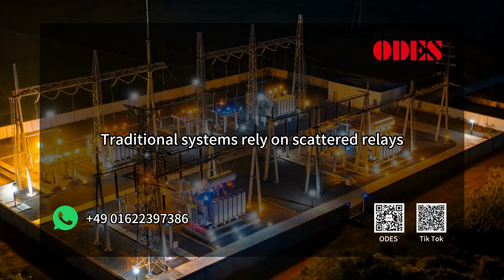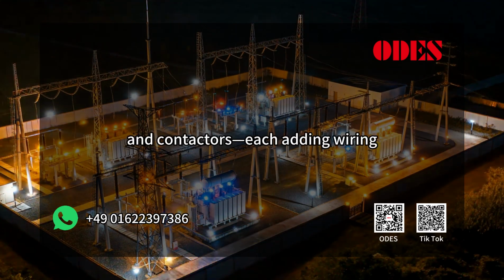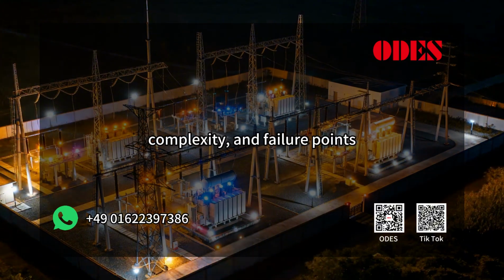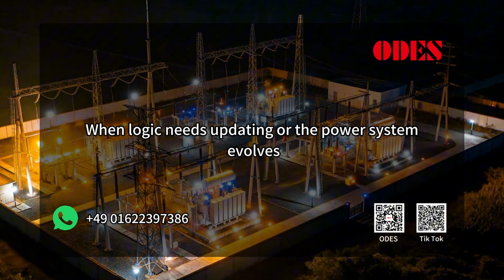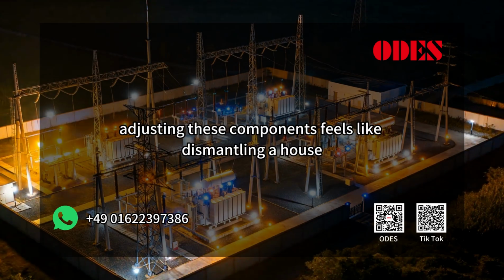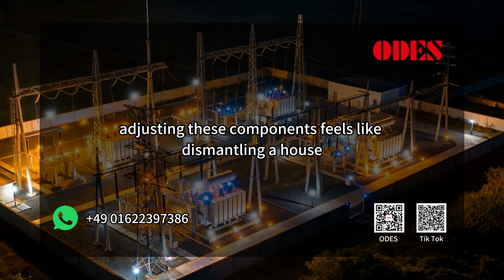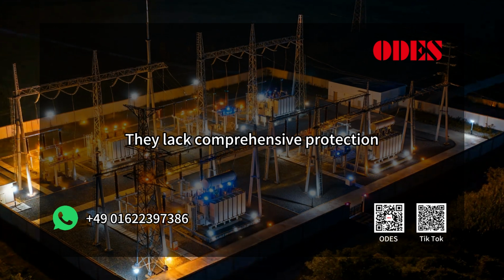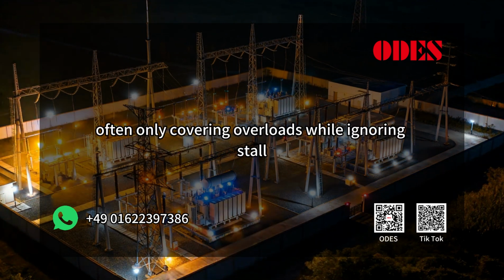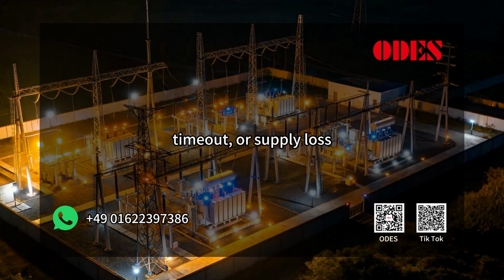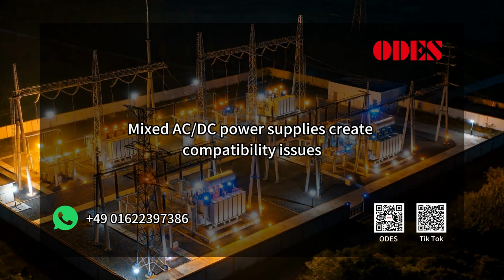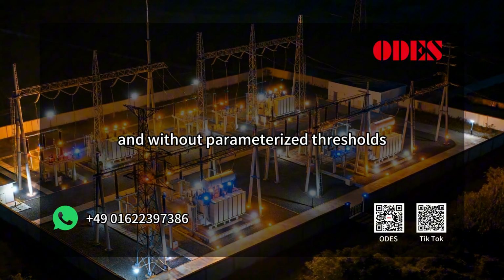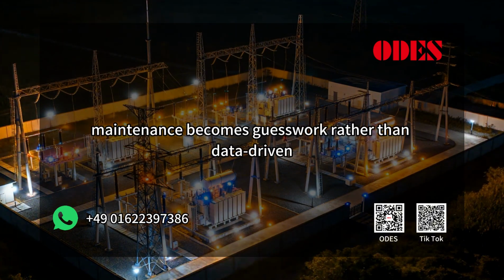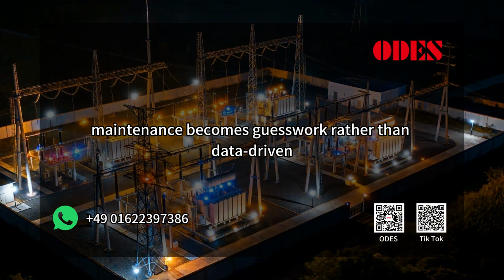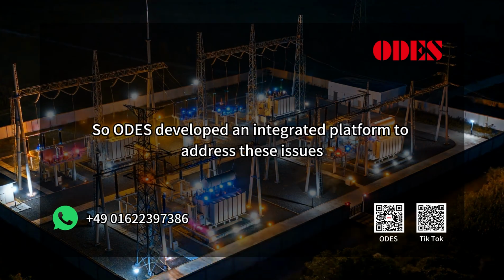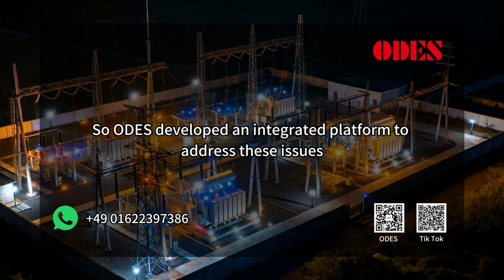Traditional systems rely on scattered relays, timers, each adding wiring, complexity, and failure points. When logic needs updating or the power system evolves, adjusting these components feels like dismantling a house. They lack comprehensive protection, often only covering overloads while ignoring stall, timeout, or supply loss. Mixed AC-DC power supplies create compatibility issues, and without parameterized thresholds, maintenance becomes guesswork rather than data-driven. So ODES developed an integrated platform to address these issues.